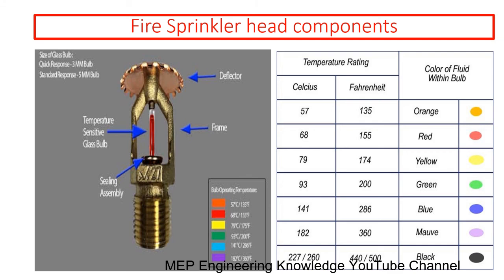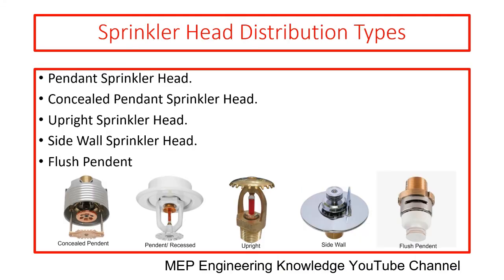So sprinklers will be used in all places, from residential to industrial purposes. Hope this tabular column will help you a lot to understand during selection of sprinklers. We will see the sprinkler head distribution types. So there are a few types of sprinkler heads: pendant sprinkler head, concealed pendant sprinkler, upright sprinkler head, sidewall sprinkler head, and flush pendant. Depending upon the usage or aesthetic requirement, you can select one of these. But the function of all the sprinkler heads remains the same.